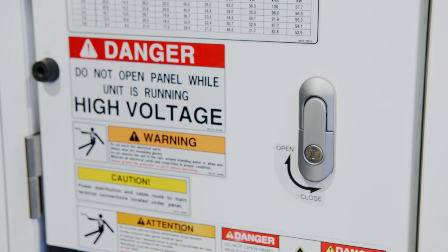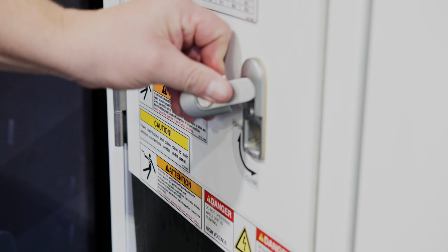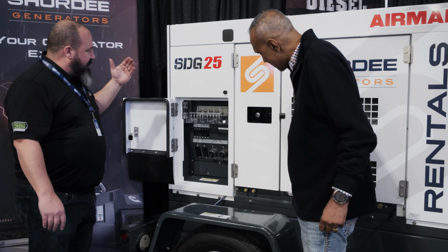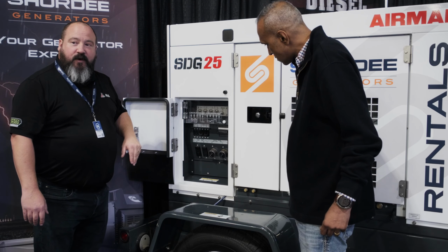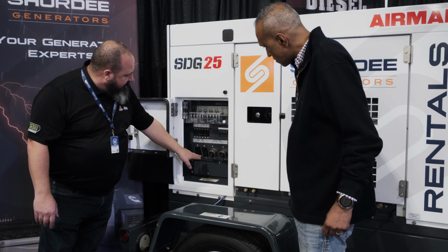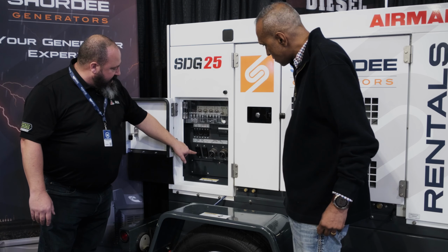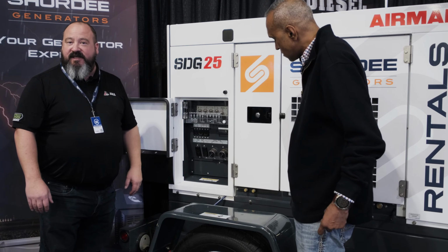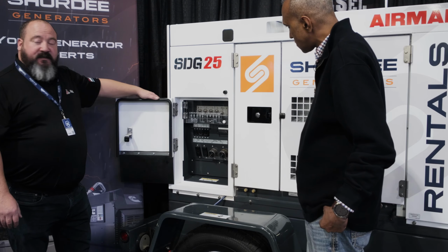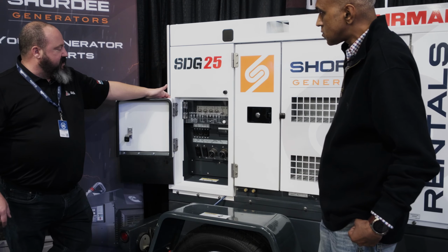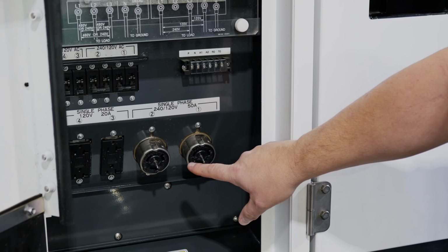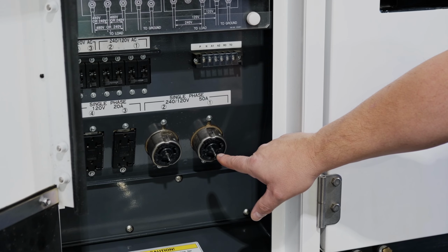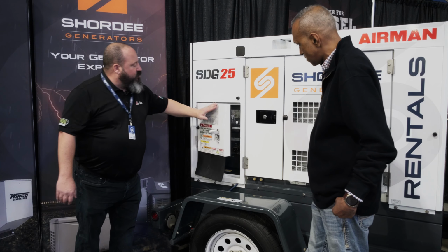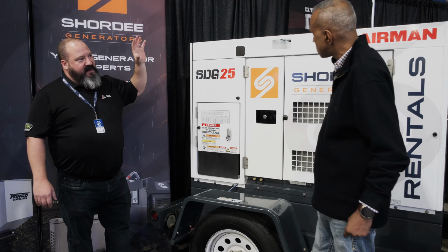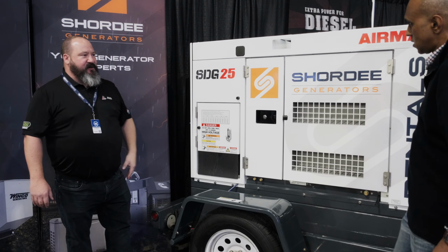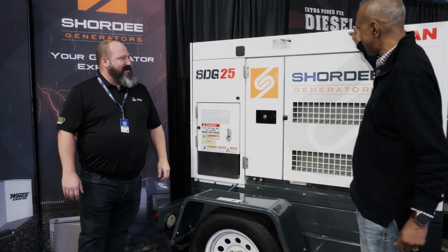So, nice lockable door for the danger zone. All right, this is where the power comes out. Open up right away, you'll notice that we have our standard lug configuration for connection, but we also have our single phase connections as well, with two 50 amp and four 20 amp connections for our single phase. This generator is capable of doing both single and three phase in voltages of 120/240 single, 277/480 three phase, as well as 120/208 three phase. One last thing is these are all powder coated so that they will look good and last and stand up for years to come. I know that because I was wiping it down. I cleaned it all up nicely.